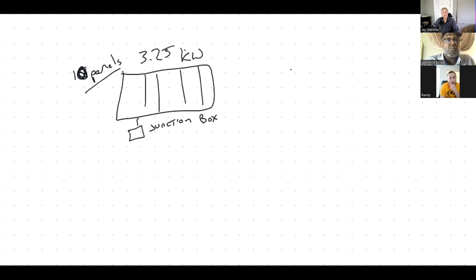Now, the proprietary cable, the first thing we need to know if we're going to use microinverters is that the microinverter we picked, the IQ8, has 13 panels maximum in a circuit. We're not calling it a string because it's parallel connections.